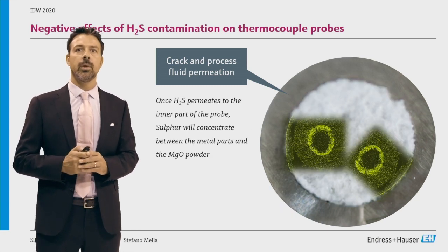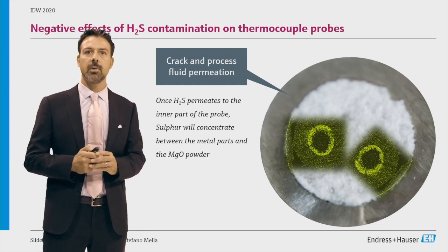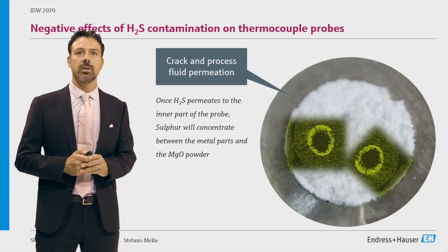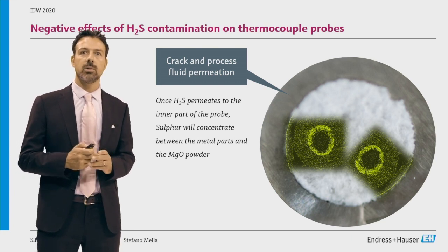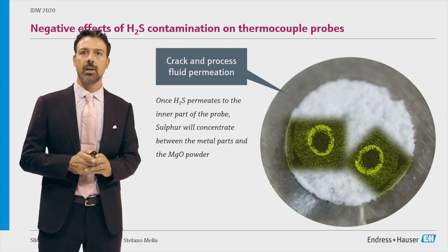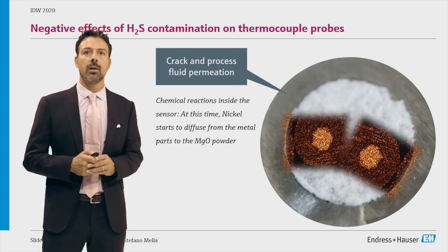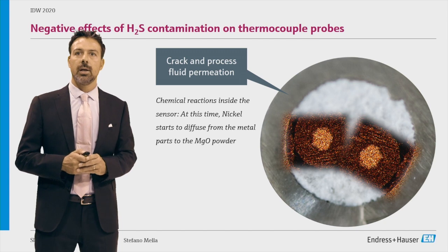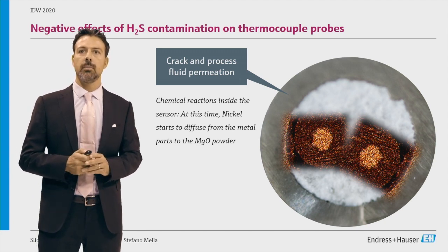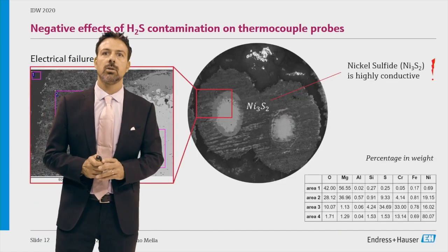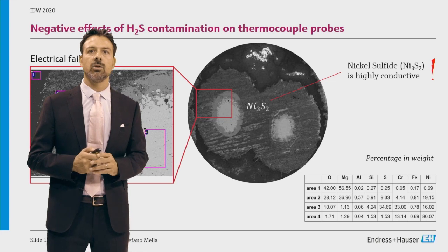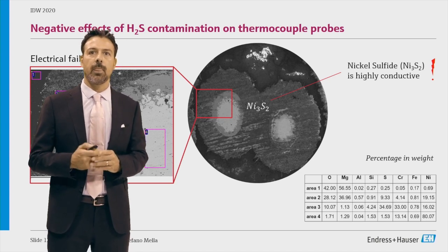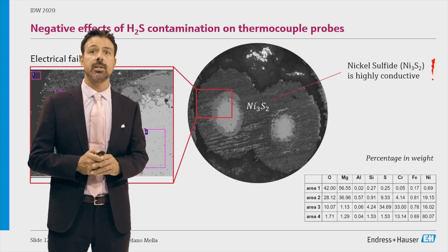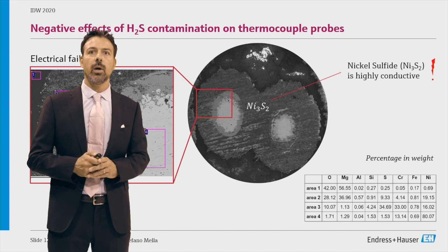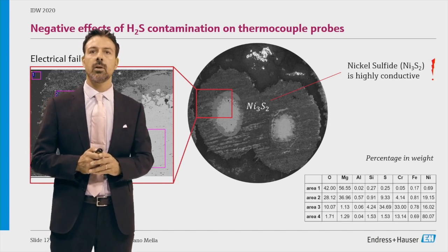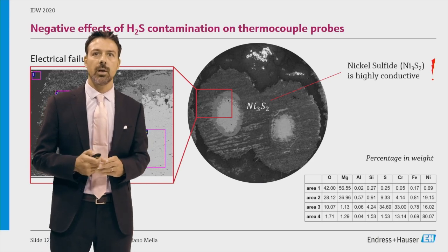Here, together with the laboratory, we have tested what the consequences are from the chemical point of view. In yellow, you see the sulfur content, and you see that the sulfur diffused in areas where it is not supposed to be, for example, in the mineral insulated powder. And if we look at the nickel, a typical chemical element of the metals, here the nickel diffused from the metal parts to the mineral insulated powder. Those of you who are chemical experts know that nickel and sulfur might cause a nickel sulfide, Ni3S2, and this is very conductive. It's so conductive that it can even be more efficient from the electrical point of view than the original hot junction, creating an additional one.